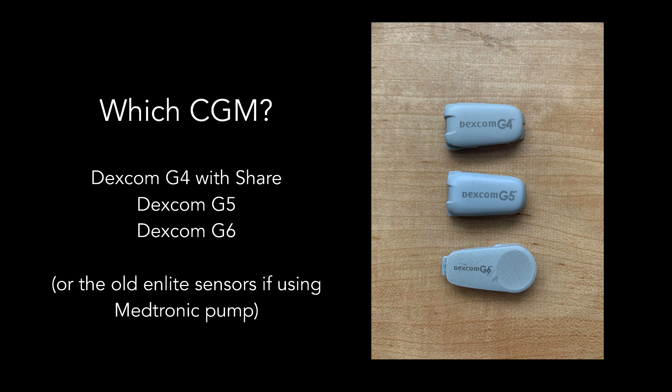Along with a compatible pump, you'll also need a compatible CGM. Most of the Dexcom series will work, including the G4 with Share, G5, and G6. Just install the Dexcom app on your looping iPhone like normal, and Loop will eavesdrop on Dexcom while it talks to the transmitter — no internet required. If you're using the old Medtronic pumps, the old Enlite sensors will also work. The newer Guardian sensors will not.